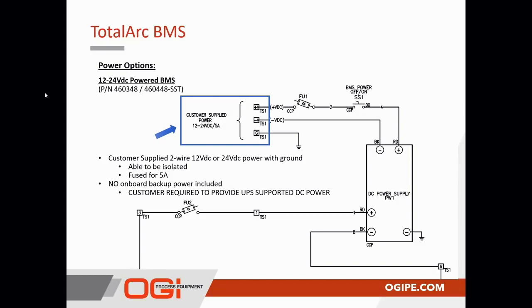Again, since this power option does not provide an onboard battery backup or a UPS, the customer will be required to provide a UPS supported DC power supply to the BMS. This power option is typically selected when installed at a customer's gate station where the electronics are powered by its own 12 volt or 24 volt DC UPS supported power. So it becomes easy just to add the small amount of power that's required of the BMS right off the gate station's RTU system.